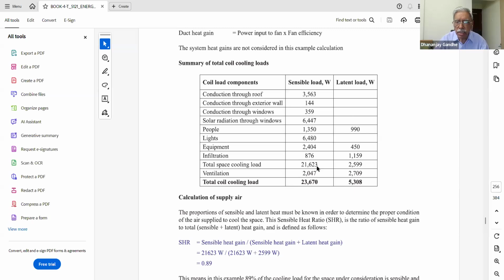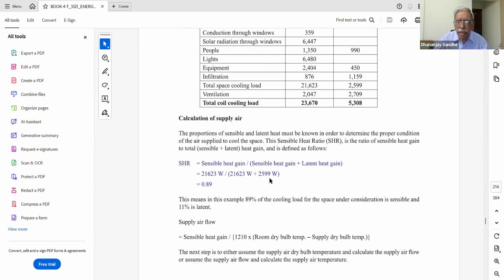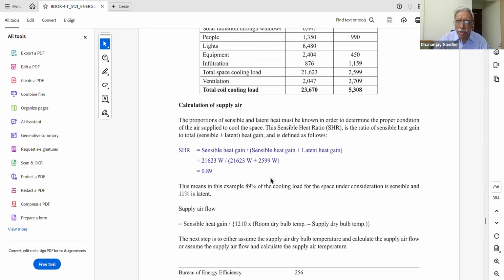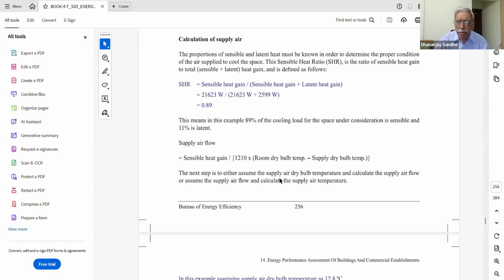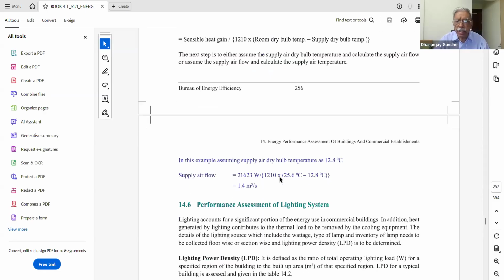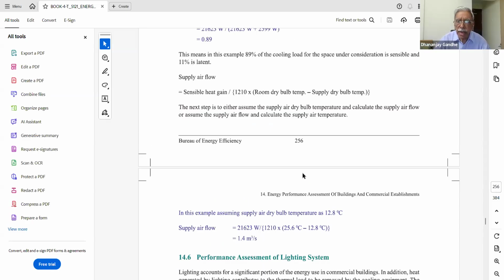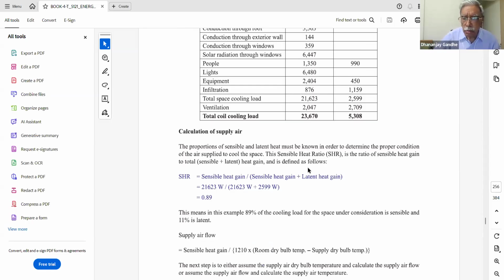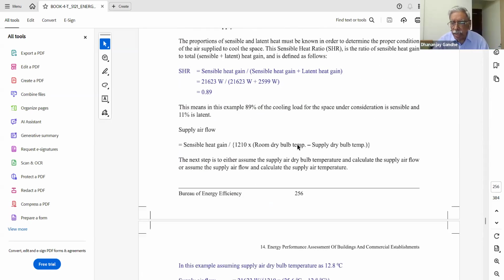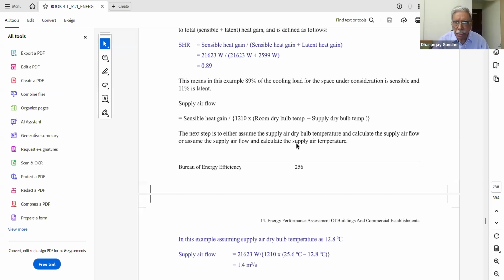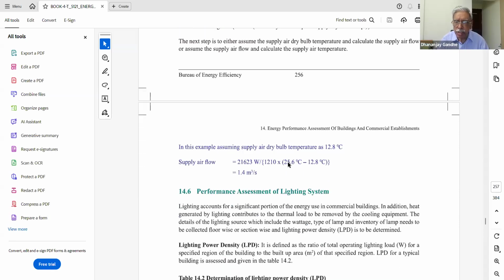So the earlier summary table had 21623 plus 2599. You add these loads of the ventilation system, and also air changes have to be done as per the ASHRAE standard. So many air changes per hour. So supply air is also to be added, and that load is to be added to this particular summary. So this is how the heat load calculations will be done for the air conditioning system. Okay, I just repeated it because this subject is one we are not very conversant with, so I thought I would repeat it. Okay.